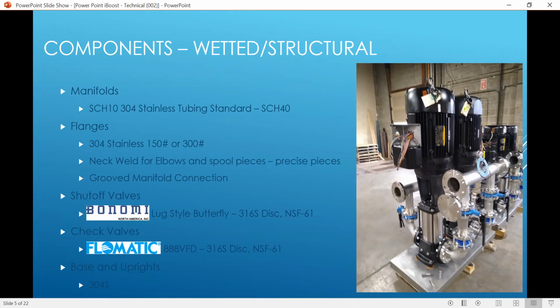If you've ever seen the threaded connections in the field on smaller units, one of the biggest problems is if you do a repair or a pump replacement, you usually have an issue balancing your headers and balancing all your elbows in the same position that they were before you took the pump off. So for ease of service, we like to use the stainless lug style connections and the flange connections on our branches. We also have a unit now that has a roll groove end, and that does save some expense, and some of our customers prefer that over the flanged ends, which we can also do.